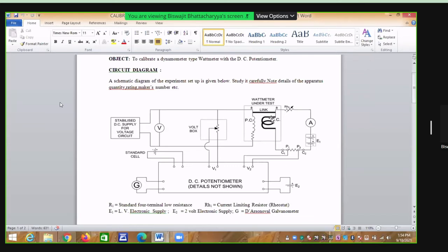So for every reading, that is for 20 watt, we will connect the link, then measure V1 and V2. We need not standardize every time. In the very beginning, our standardization will be only once to set the working current. Once it is fixed, it will hold all through the test mode, with no standardization for the rest of that particular day. So now we will insert the link. Our reading will be with link. We measure V1 and V2 with link and calculate the error, that is the difference between the wattmeter reading and the potentiometer reading after calculation.